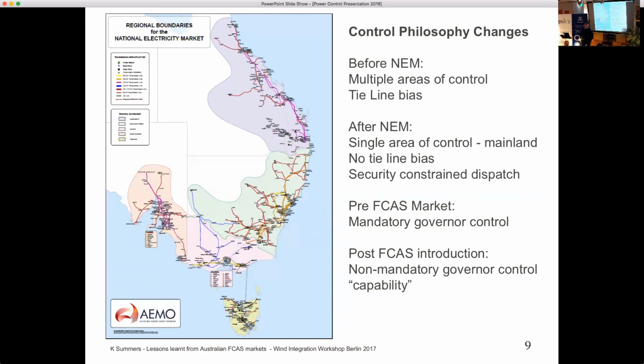No, you don't. So having wide settings on these generators and allowing the rotational speed to slow down and contribute their kinetic energy to the power system, inertia, but not supporting it with mechanical power back into those generators to keep them rotating, we can't save the system, because generally they will slow down and keep slowing down because we haven't put any arresting energy back into the system to bring them back up to speed or to keep them at speed.